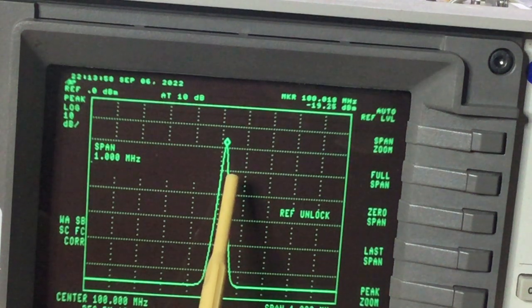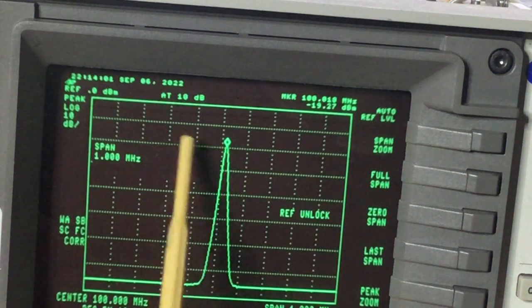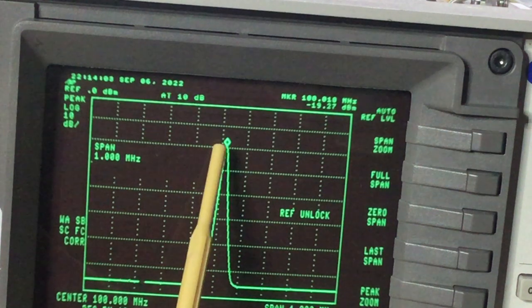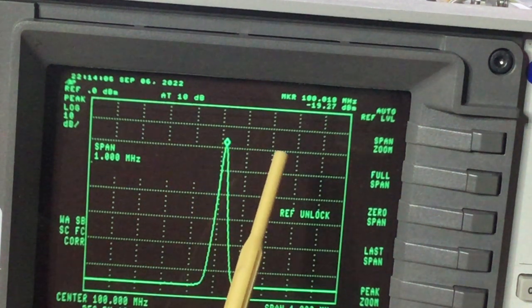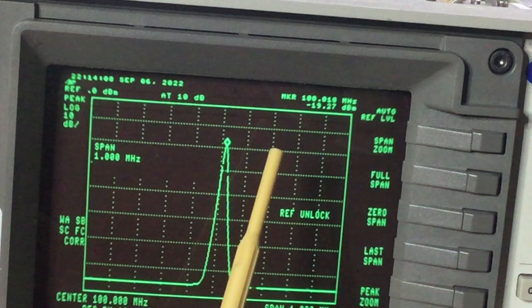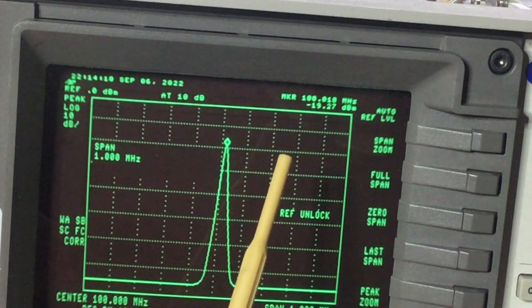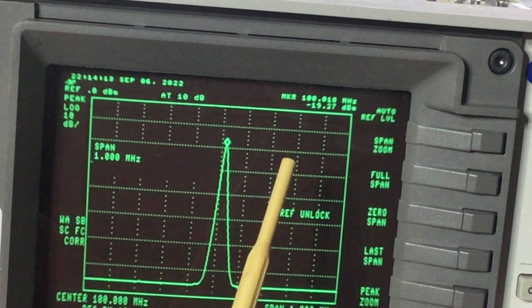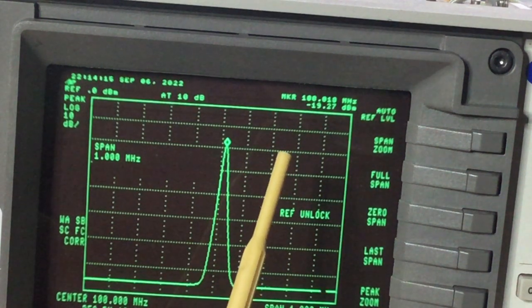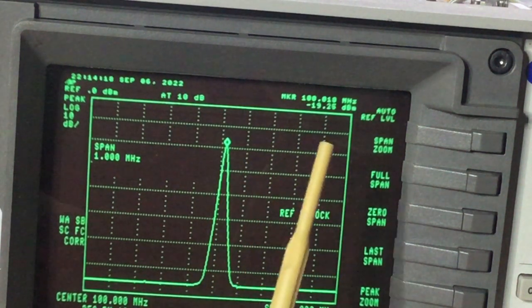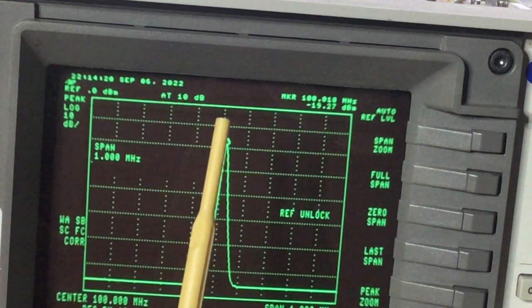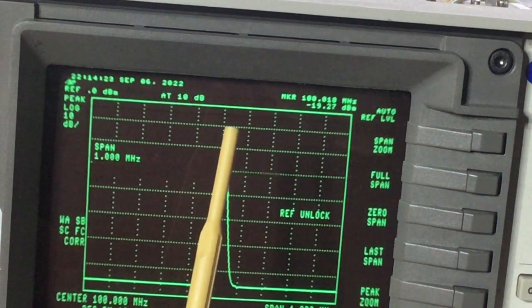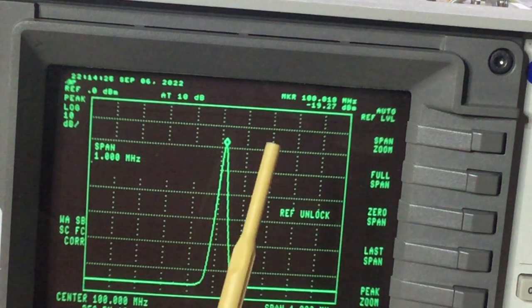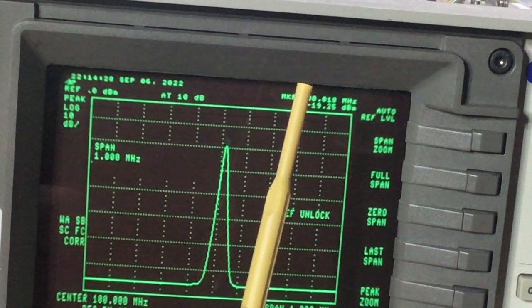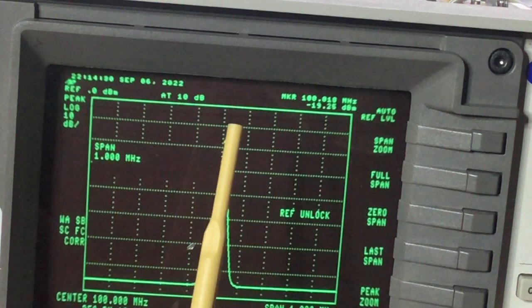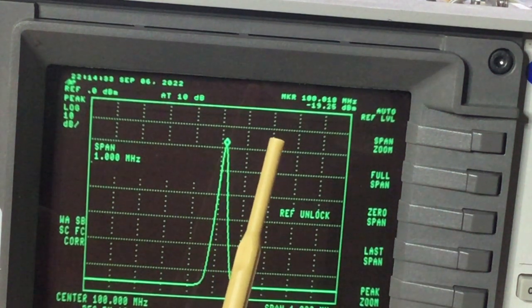Now obviously the DAC value changing in the calibration menu, the service menu on the instrument, couldn't pull the 10 megahertz oscillator about greatly. It was only a minor change here or there. So I think it perhaps needed that manual intervention in order to coarsely bring the frequency of the oscillator closer to the 10 megahertz point, before then naturally the 600 megahertz and the 300 megahertz would track with that, and therefore their frequencies would be massively changed.